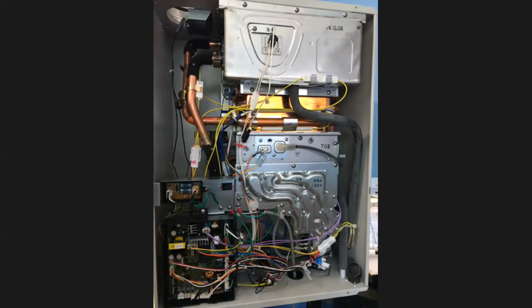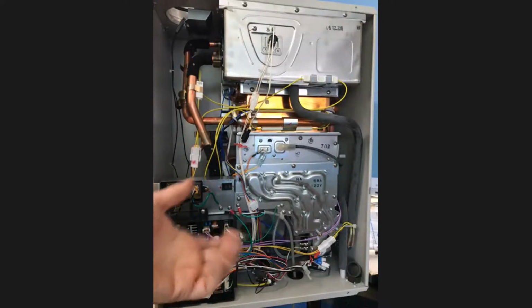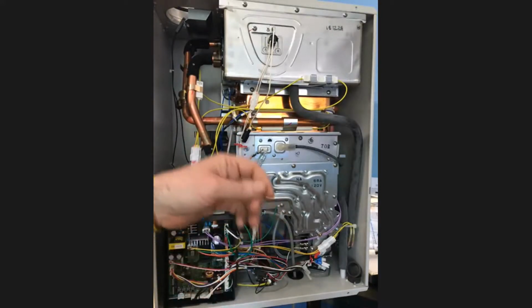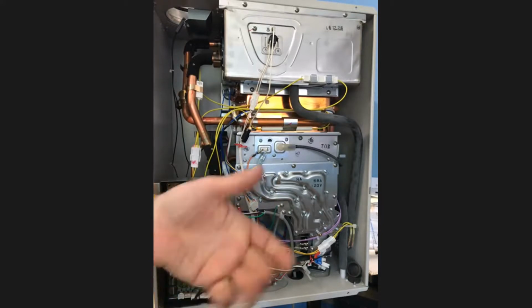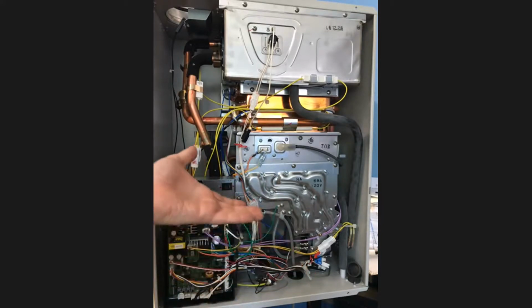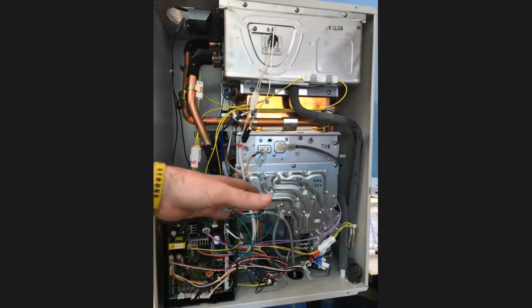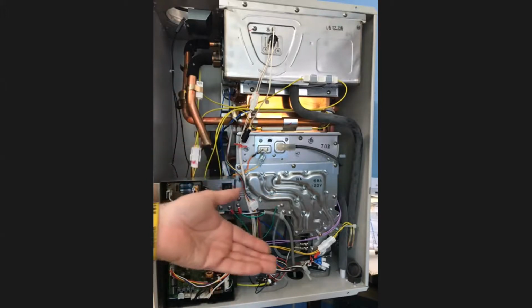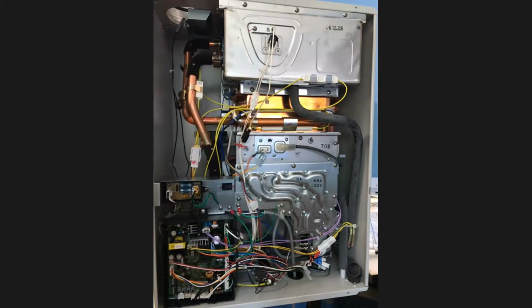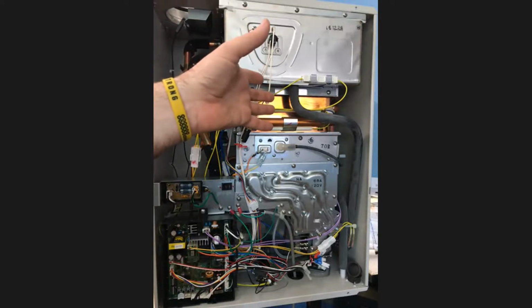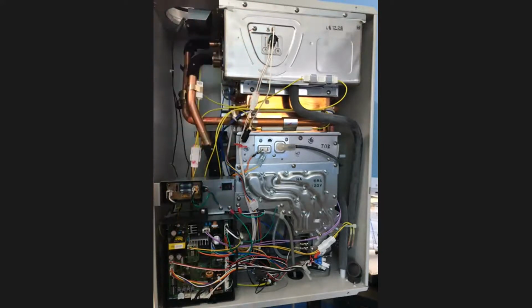We can do that because it's a tankless unit. If it were a tank type unit, I might make the scale inert, but it would sit in the tank and settle to the bottom, building up. As scale builds up inside a tank, it reduces the unit's efficiency. Because we don't get scale buildup here, the efficiency from day one stays the same one, two, three, four years down the line, since we're still transferring the same amount of energy without the insulating factor of scale to heat through.